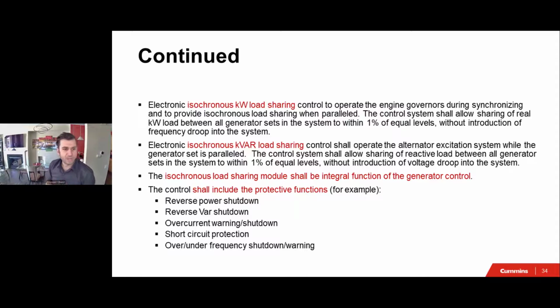And when it comes to load sharing, because that question comes up, do I want droop or do I want isochronous? Again, you probably want to resort to isochronous. So isochronous for both kW for the real power and isochronous for the VARs for the reactive power. And we don't want an independent module to do so. We want that to be part of the genset controller as well.